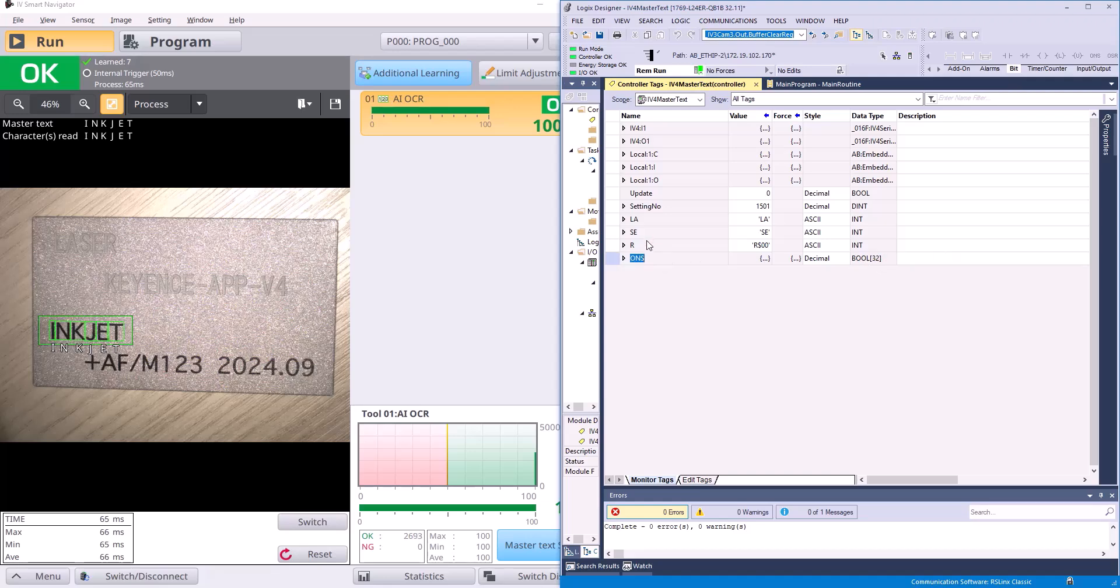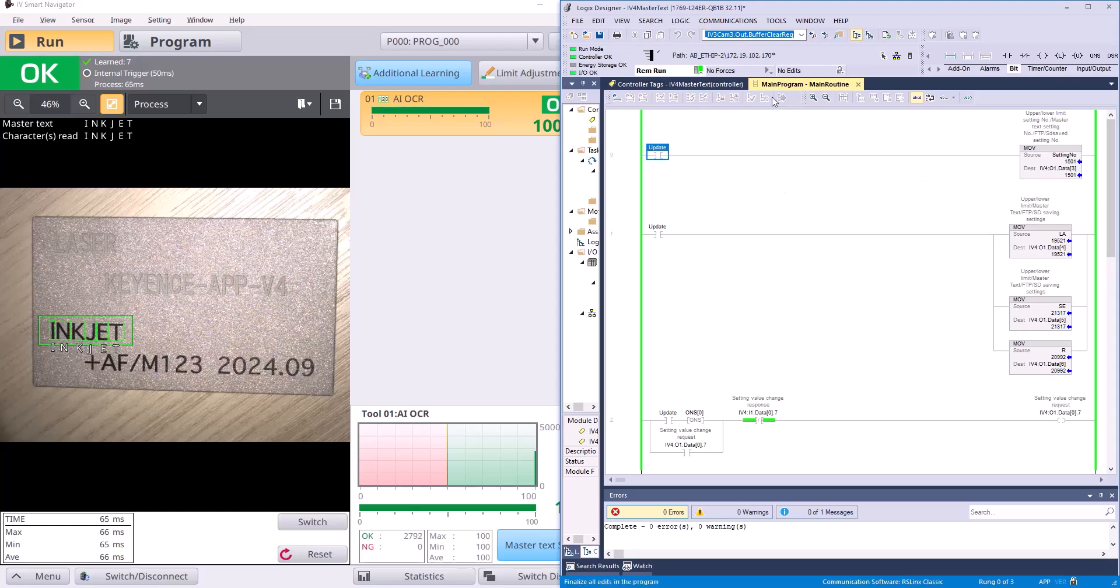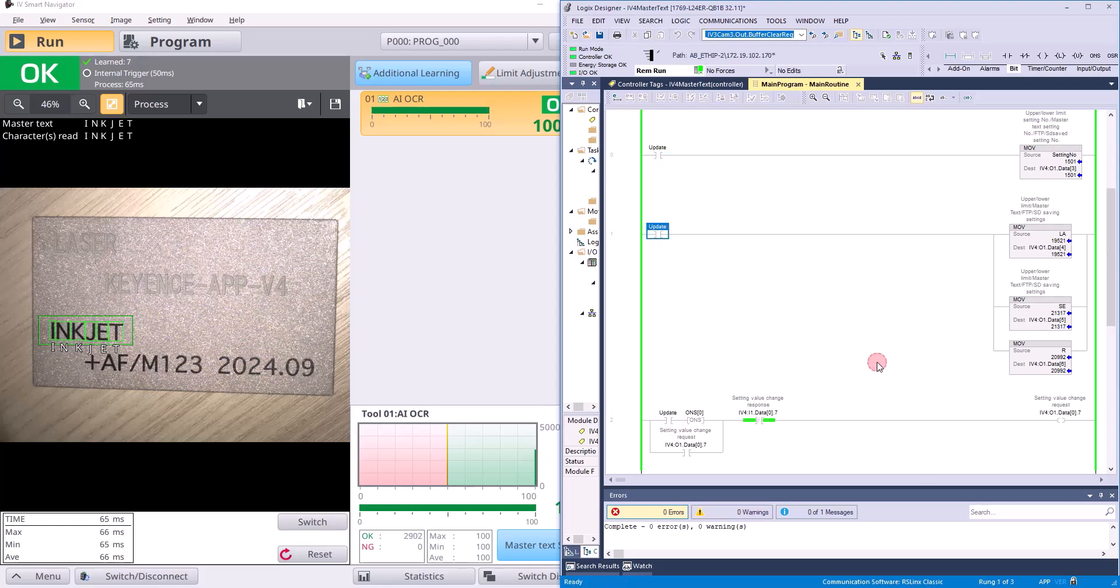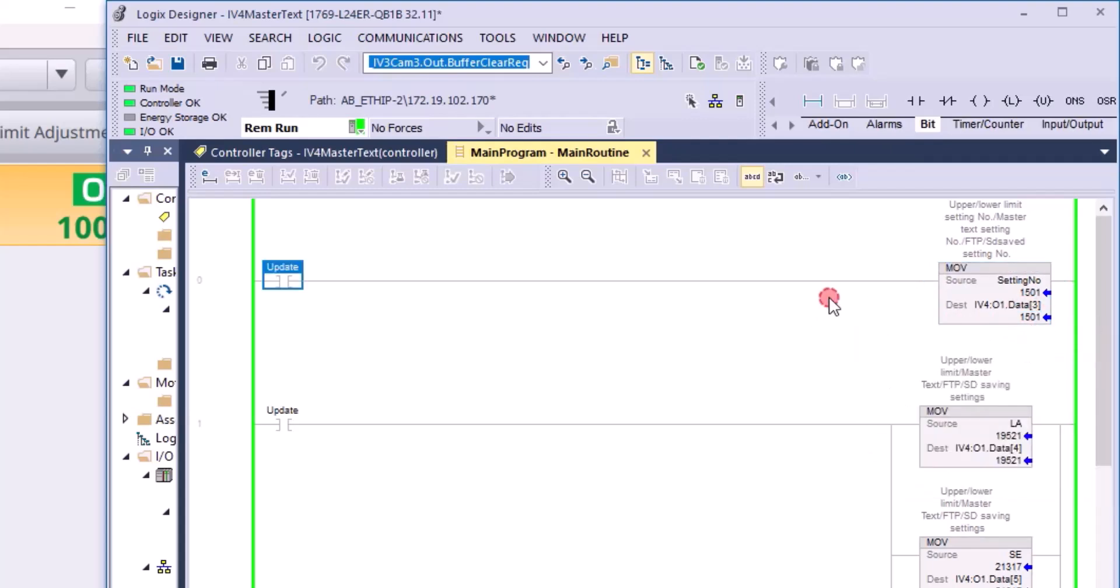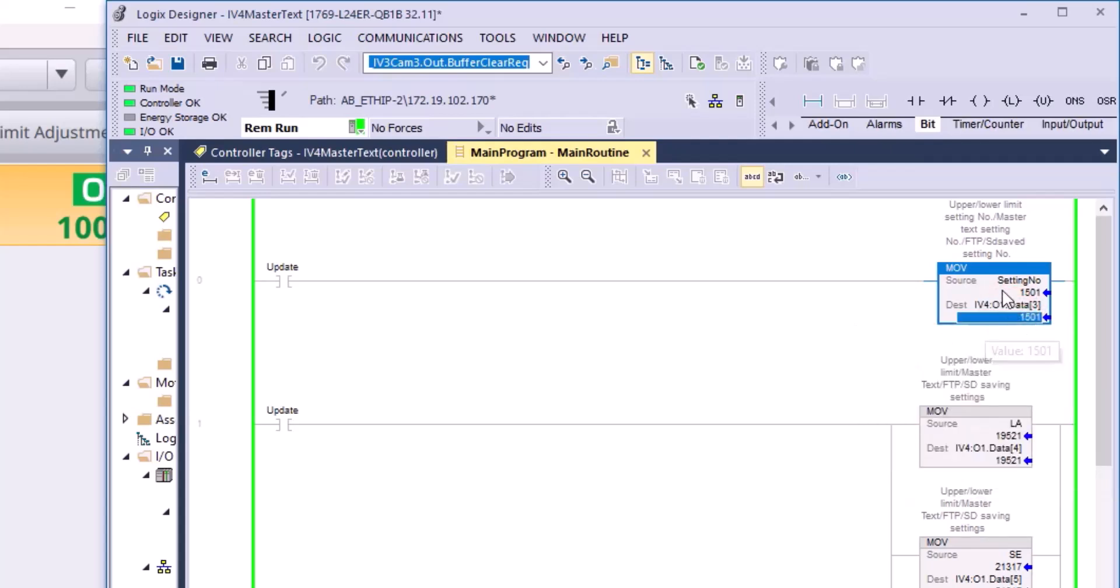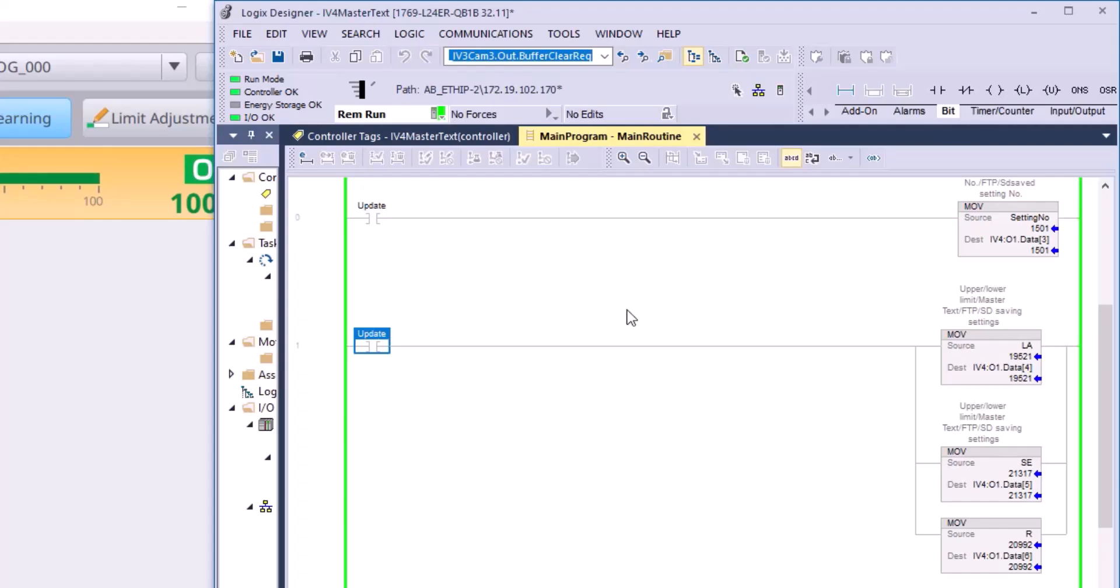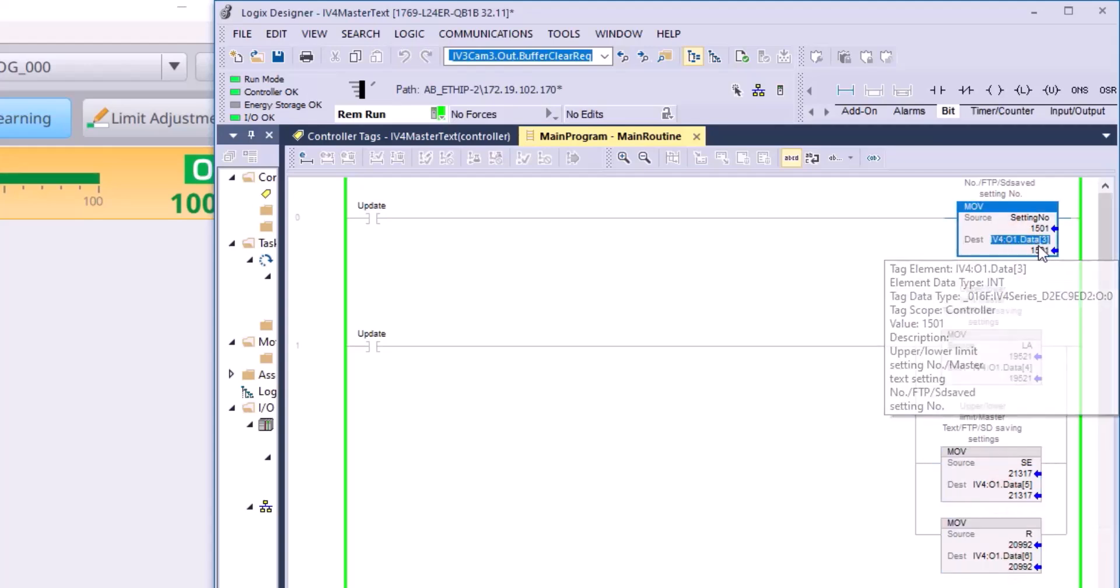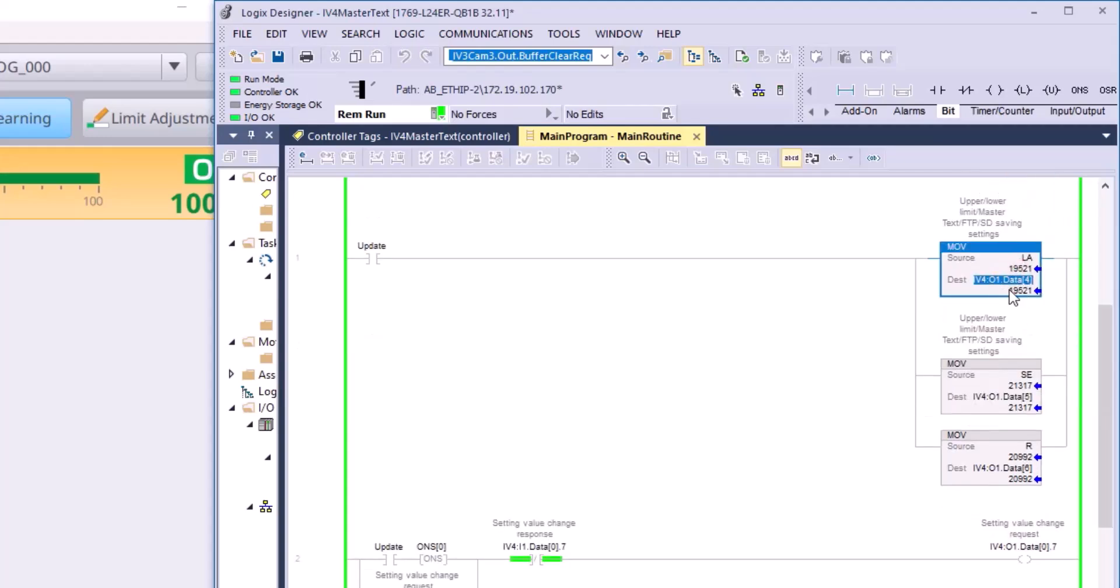I also have a one-shot bit here. It's just a bool32 to make sure that when we send our request to update the master text that it sends just a one-shot. So now we can jump into the logic and I've already got this all set up and I'm just going to explain what I've done here. Like I said, sort of this dummy update bit. When I show you how this works to update it, I'm just going to toggle that on and it'll activate all three rungs of logic which is exactly what we want. So first thing it does is it moves that setting number into data 3. Now I had already done this a couple of times in practice beforehand so it's already been moved in there. In your case, usually this output data 3 is just at zero with nothing there to start so we have to move in our setting number so it knows what kind of change it's going to make. Our next rung here, we're going to move our words into our IV4 output bits. So IV4 output data 3, that's the setting number so it knows what kind of change it's going to make. And then 4 will take the first two letters of the word you want to update to. 5 will take the second two and 6 will take the last one in this case.